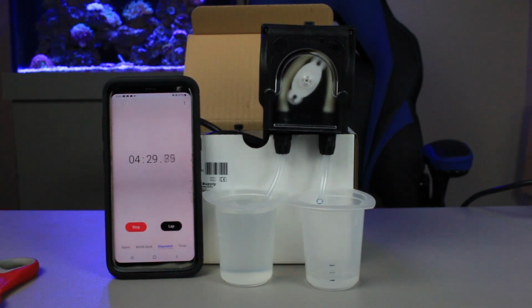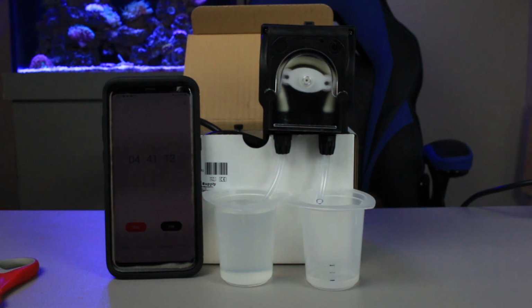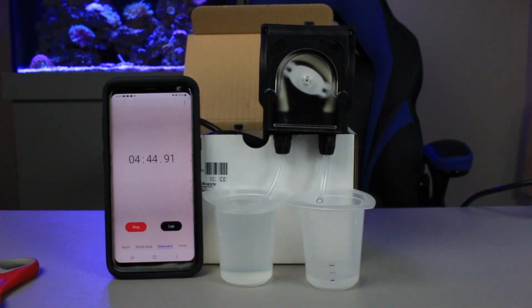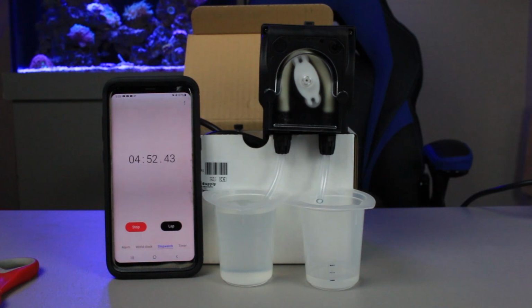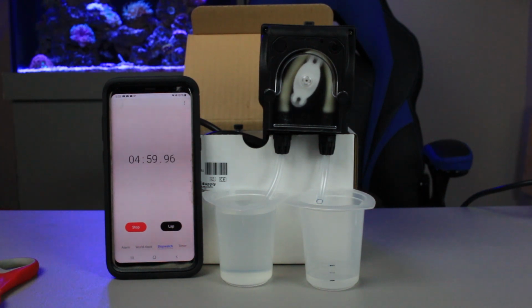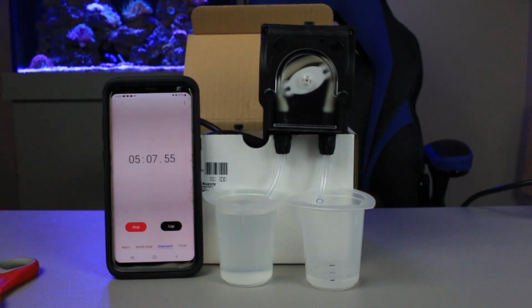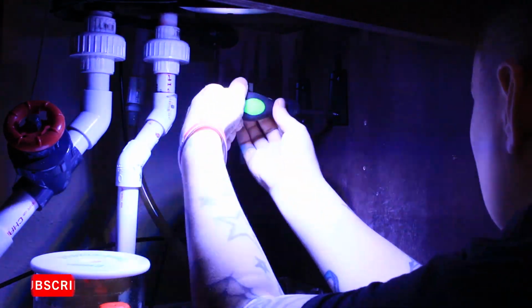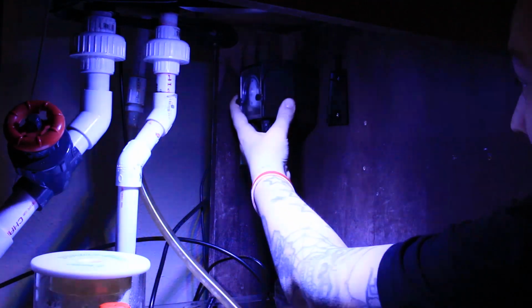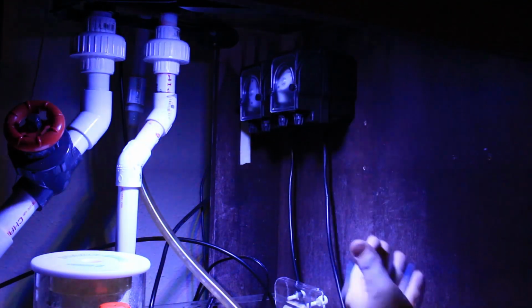So on my first initial calibration, this pump produced 20 milliliters in 10 minutes. So what this basically means is this pump is running just a little faster than what BRS says it does, which is not a bad thing, but I just needed to be aware that this pump does actually run a little faster. So I'm not setting the pump to dose for 10 minutes and expecting 10 milliliters when in fact it'll actually dose 20 milliliters. All right, so there's 5 minutes, and we are at exactly 10 milliliters. There we have it.